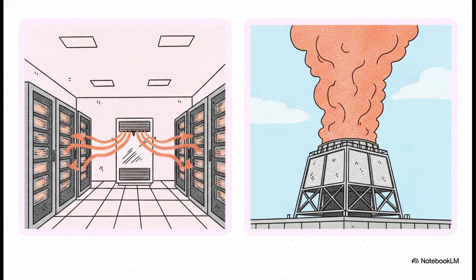On the inside, we're talking about an indoor cooling unit measured in what's called a refrigeration ton. But on the outside, we use an outdoor exhaust unit, known as a cooling tower ton. Sure, they both use the word ton, and yeah, they both measure cooling capacity, but they are completely different beasts. One measures the heat ripped out of your office, and the other measures the heat dumped off the roof. To figure out why matching them breaks everything, we've got to look at what each side is actually doing.